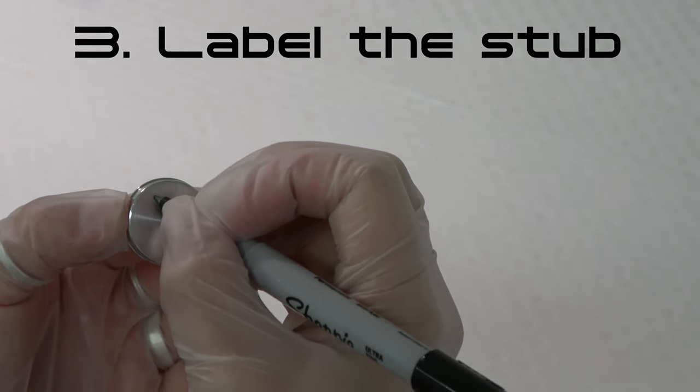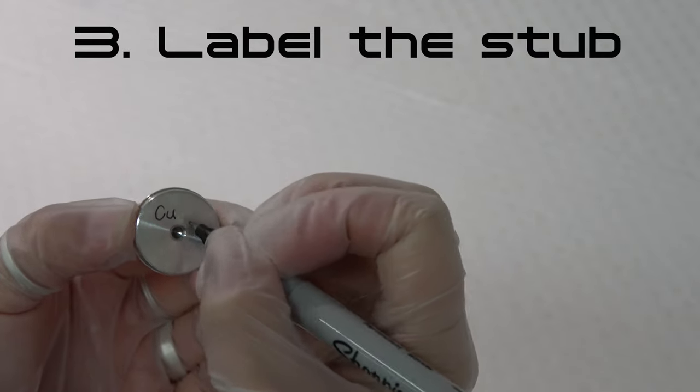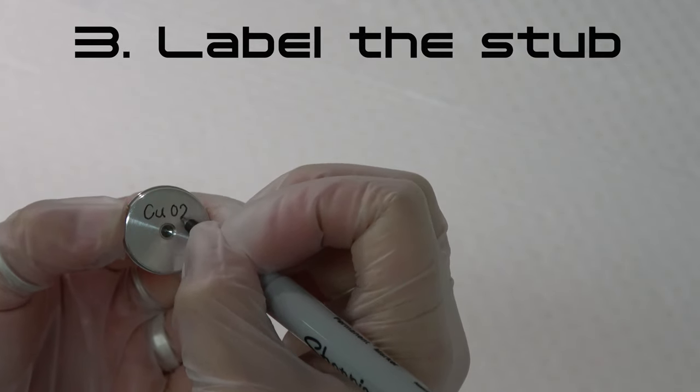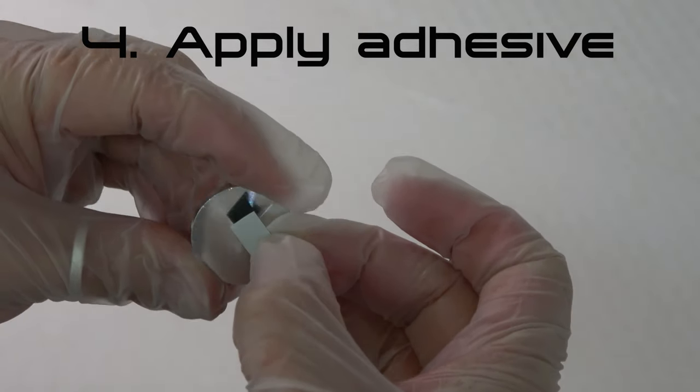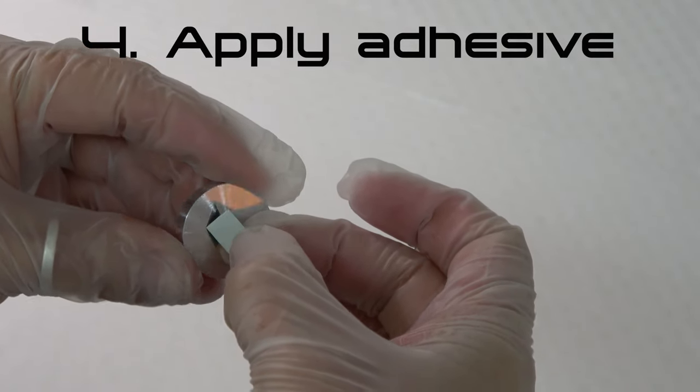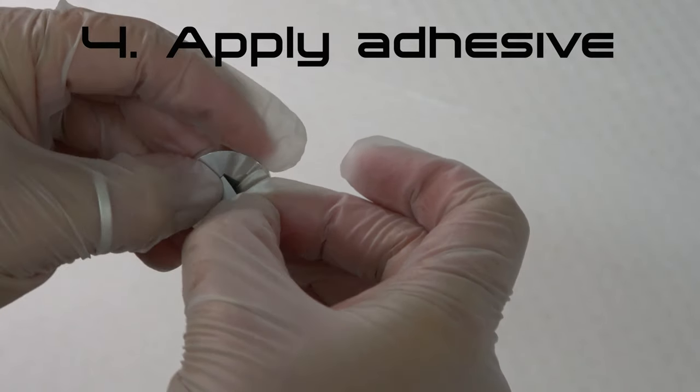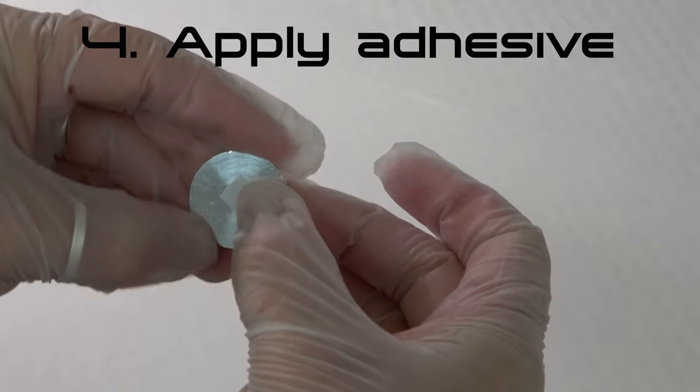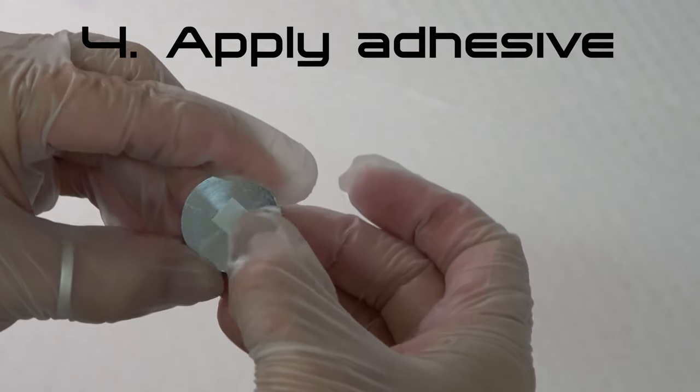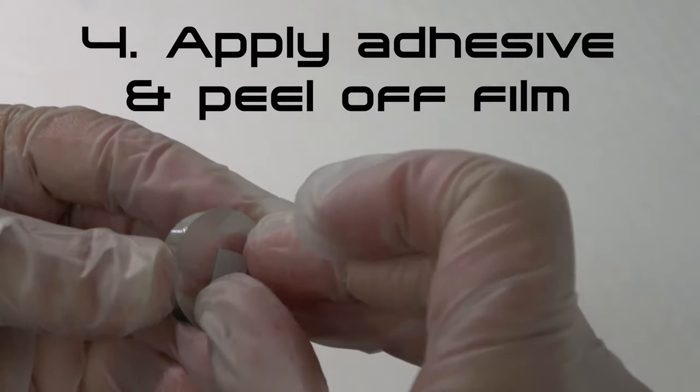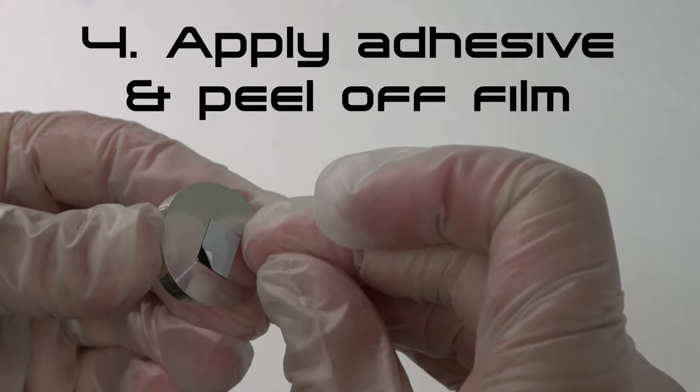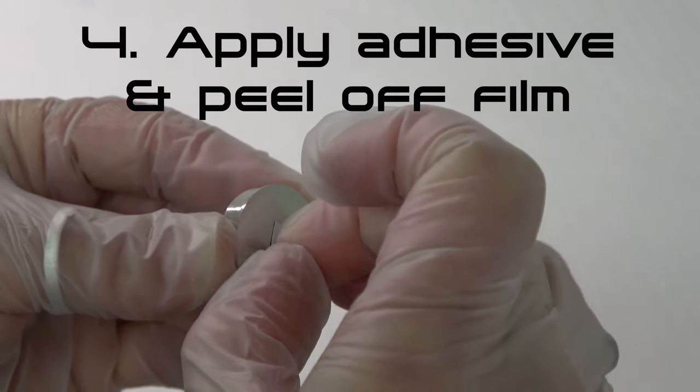Step 3: Label the underside of your SEM stub with the sample name or ID code. Step 4: Place one side of the double-sided adhesive onto the SEM stub. Use only enough adhesive to ensure that the sample can be securely attached to the stub. Remove the protective film to expose the surface of the double-sided adhesive.